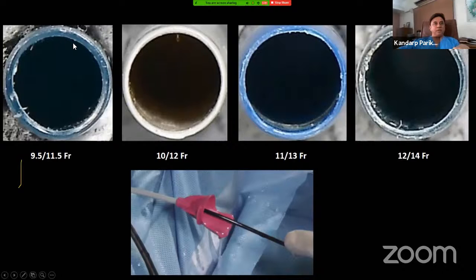Now you can see here, this is the inner lumen of the ureteral access sheath. This is a 9.5 by 11.5 French ureteral access sheath. This is 10, 12, 11, 13, and 12, 14. These are the 4 sizes of ureteral access sheath we normally use. Whenever you use a ureteral access sheath, it is important that there has to be adequate water return. It is not enough that the water goes in; it also has to come out. So there has to be a difference of at least 2 French between the diameter of the flexible scope and the inner diameter of the ureteral access sheath, the inner sheath.